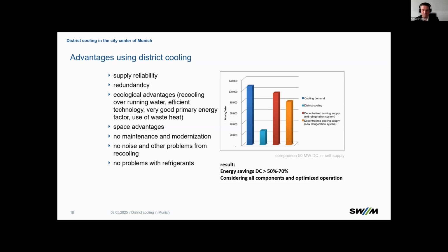And as you can see, the megawatt hours per year are on the left side, and the energy need for supplying that cooling demand over district cooling is the light blue. In comparison to that, the red and yellow ones are the self-supply with old and new machines. As you can see, we have energy savings with the district cooling of around 50 to 70% compared to self-supply. That includes all components like the pumps and so on.